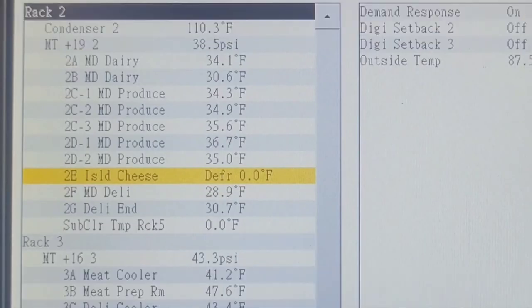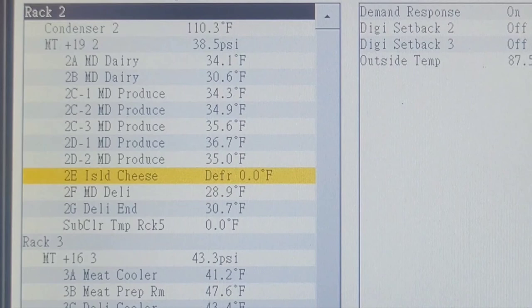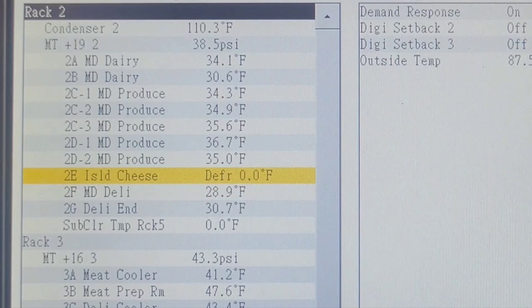So this call's done. Real simple job, just got to know what to look for, don't let it intimidate you. Just a simple adjusting of the EPR valve on this particular case, like about a half a turn, that's all I did. Hope you guys got something out of it, enjoy. Try to make another video on my next call if it's worth it.